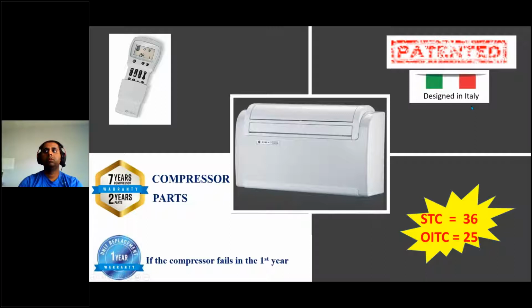And one of the things that you got to remember is in Italy and in France and many of the European countries, you cannot mount a unit like a mini split outdoor unit or put a window unit in a wall. They won't allow it because it just destroys the architectural feel of the building. And so they don't allow that, but they do allow this. That's why this was originally designed and marketed in Italy and all of Europe, because people could get air conditioning and heating affordably without having to do all this refrigeration work and have very little impact on their building.